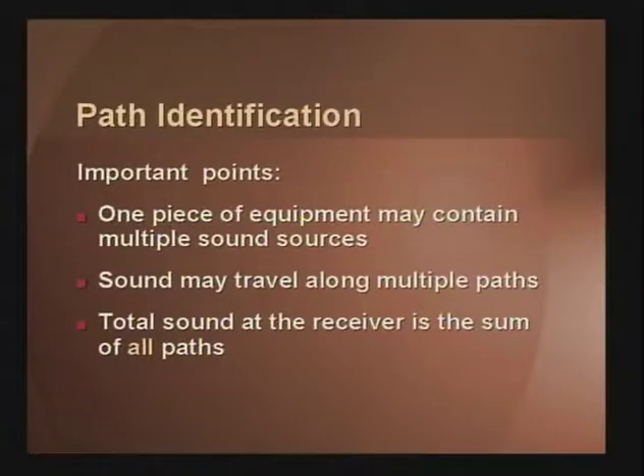Really depends on the type of equipment that you have, how your sound paths will come out. It may be very simple. Important points to remember are that one piece of equipment may contain multiple sound sources. You may have a supply fan and a return fan in the same unit, or there may be compressors or other sound sources in that unit. You also have to look for all the different sound sources that may be affecting that space. Make sure that you realize that sound may travel along multiple paths from a particular source to the space. And then finally, it's the sum of all these sound paths that determine the sound level in the space.